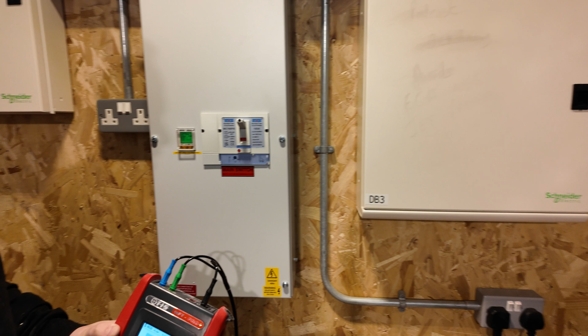In the real world, this isn't how you'd have it set up, but I've programmed this one to 100 milliamps, which is why I jumped to the 5 times test at 150 milliamps to see what went first. Obviously, the other RCBOs in circuit are 30 milliamps.